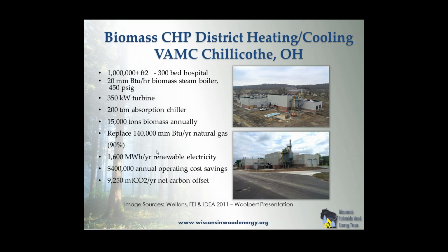They're generating 450 psi gauge steam in the system, with a 350 kW turbine. Their current price and distribution, everything for natural gas, is in the $7 range, and they still have substantial savings. When we did this project, natural gas obviously was higher, but they are still considerably better off running the biomass system than natural gas. Again, their net distributed cost for natural gas last year was right at $7 a decatherm.